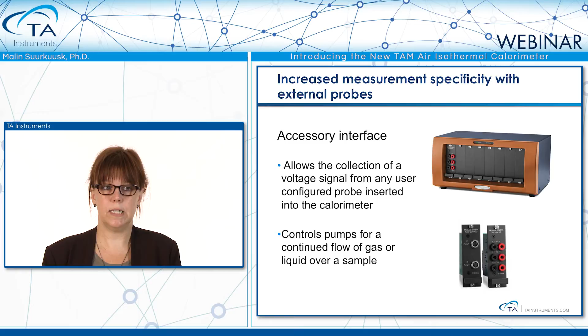What is also new with the new TAM Air is that we have the possibility to collect other signals to make the measurement more specific. You can configure your TAM Air with external probes, and the signal from this probe can be connected to the accessory interface and collected at the same time as the heat flow data. In this way, you make the non-specific heat flow data more specific if you can connect it to maybe a pH probe or oxygen probe, to see what's going on inside the calorimeter. So in the accessory interface, you can connect what we call the voltage in-out box, where a voltage signal from any of these user-configured probes can be collected at the same time. As well, we have a pump control module, where if you need to pump fresh air or medium through the ampoule, it's possible to control that also from the software itself.